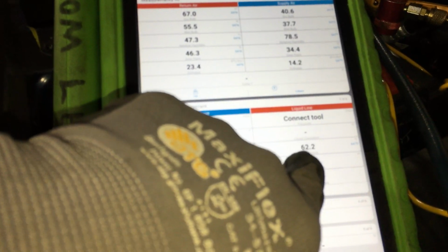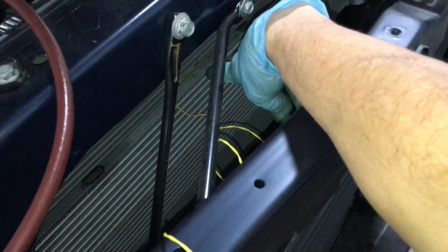try to get you a picture. You can see right there where the liquid line goes inside the vapor line, the suction line, to cool off that liquid. Now the temperature of that liquid right now is 62 degrees. But wait a minute, what's the outdoor bulb temperature? About 62 degrees. So that temperature is taken from this thermistor that's right here of the air temperature going over the condenser. The liquid line temperature out of the condenser is taken at this temperature right here on the liquid line right there.